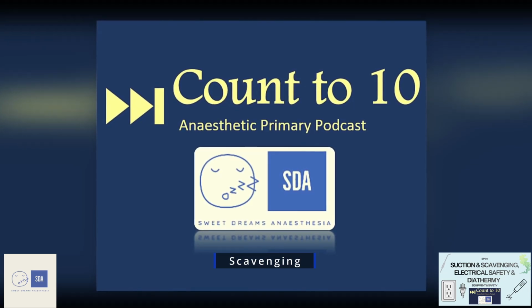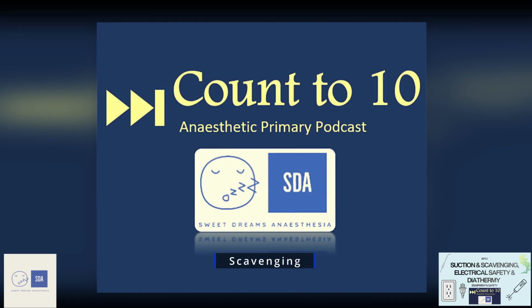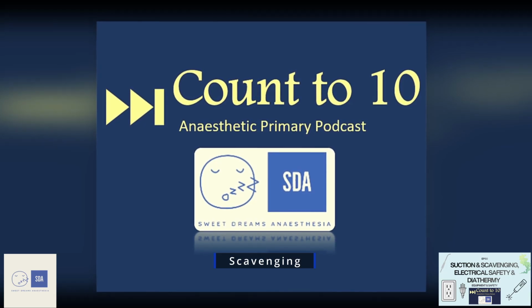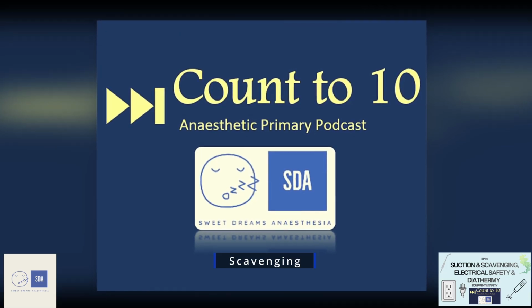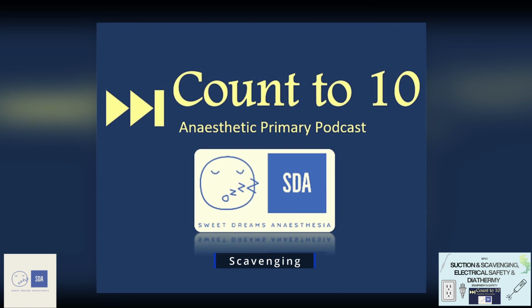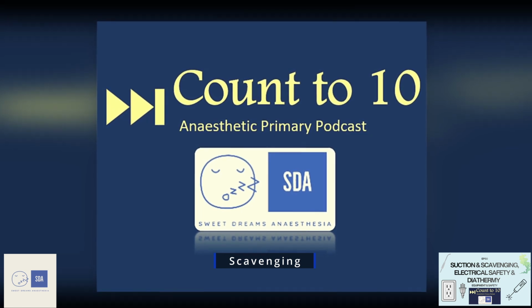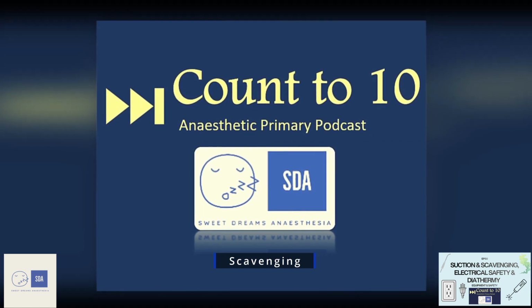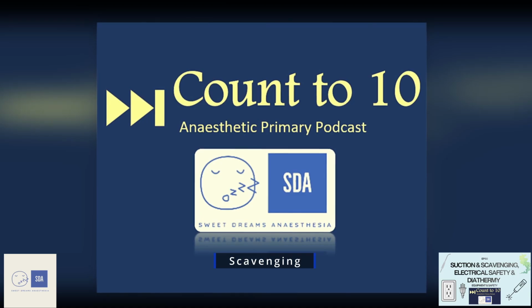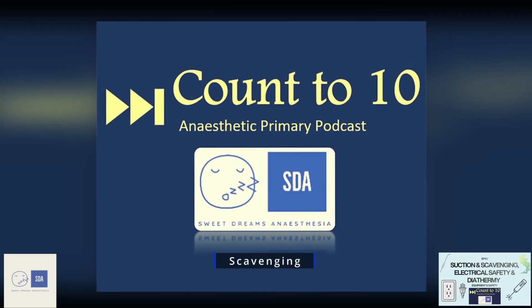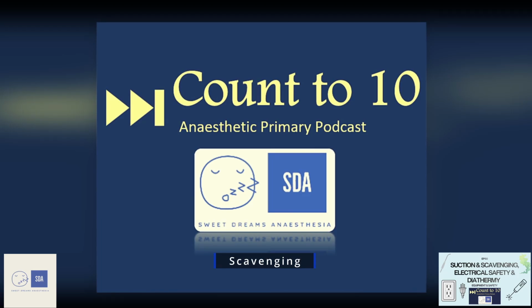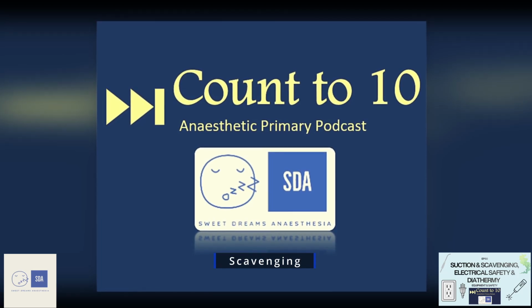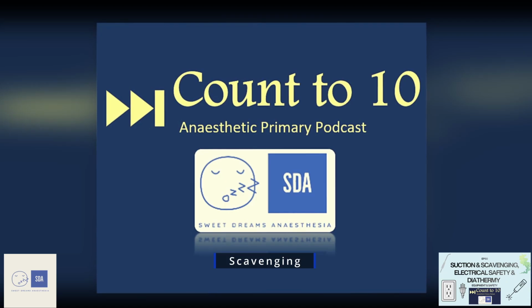Then you have the next component, which is the transfer tubing, which simply just transfers the waste gases into the receiving system, the scavenging interface. The specific thing with the transfer tubing is that it's a certain diameter of 30 millimeters to ensure that you don't get any accidental cross connection. From here, you get to your receiving system, aka your main place where your scavenging is working.